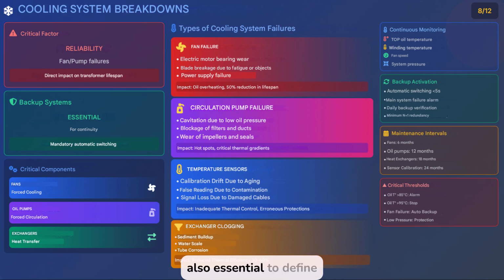It is also essential to define clear thresholds: alarm at 85 degrees, shutdown at 95 degrees, automatic backup activation if a fan fails, and low-pressure protection. Ultimately, cooling is not an auxiliary. It is life insurance for the transformer. Monitoring its thermal performance with a predictive approach not only prolongs the asset's life, but also protects the investment and improves long-term profitability.